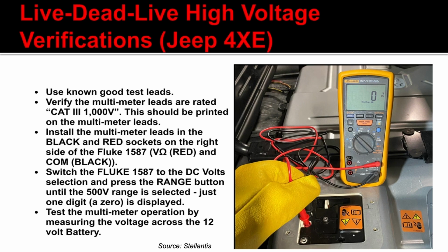The manual tells you these gloves aren't insulated, by the way, these are the shells covering a set of high voltage gloves. The technician is using the meter leads to probe into the test ports, which are 4 millimeter. They don't tell you that in the manual, but they're 4 millimeter, designed for the lantern tips that a lot of meter tips have.